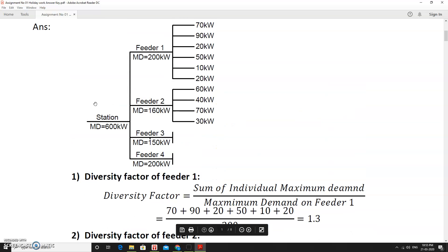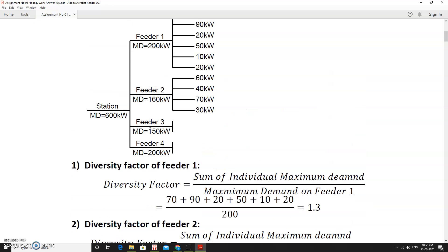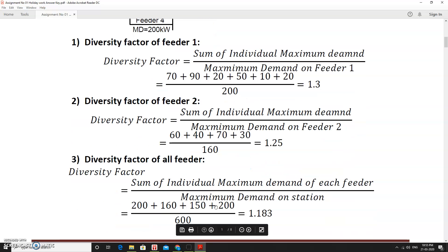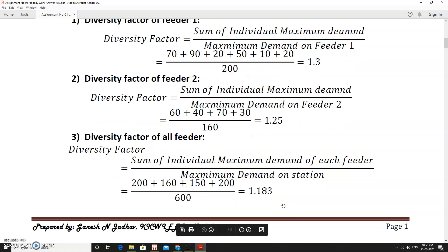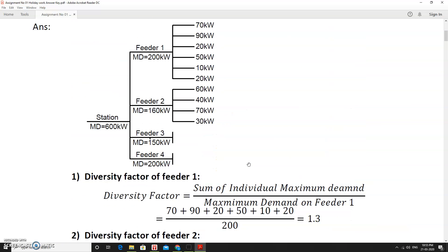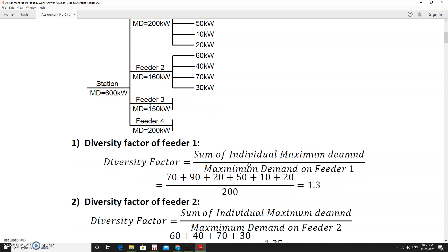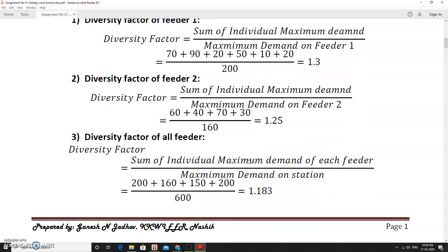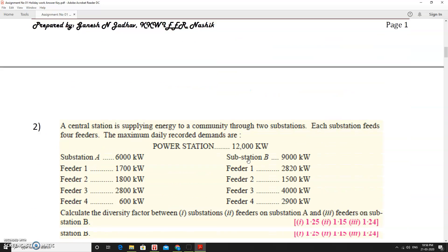To calculate the station diversity factor for all feeders, we take the sum of individual maximum demand of each feeder: 200 + 160 + 150 + 200, divided by the station maximum demand of 600. This gives 1.183. As a cross-check, the diversity factor is always one or greater than one.